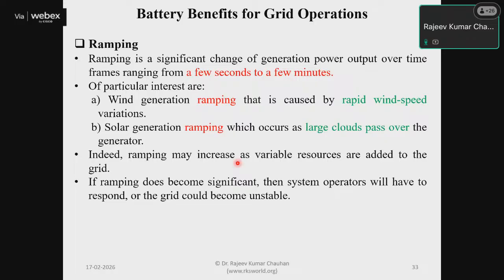So ramping may increase as variable resources are added to the grid. If this ramping becomes significant, the system operator will have to respond, or the grid could become unstable. Sudden generation increase, sudden load increase, or sudden outage of a plant may cause frequency and voltage variations in the grid, or power mismatching, which may cause blackouts.